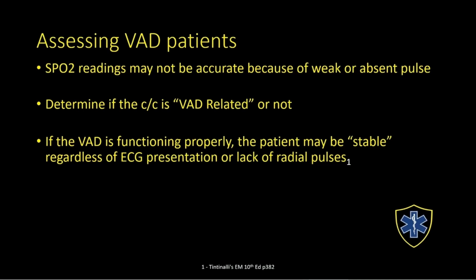But if the VAD is functioning properly, the patient may well be perfectly stable regardless of what we see on the monitor or the lack of radial pulse, and it may be just something that can be treated at any facility, any hospital. If, on the other hand, the problem is a VAD malfunction, or it's not functioning, or the patient is extremely hypotensive, or they're unconscious, they're not perfusing their mental status adequately, those would all be likely VAD-related incidents.